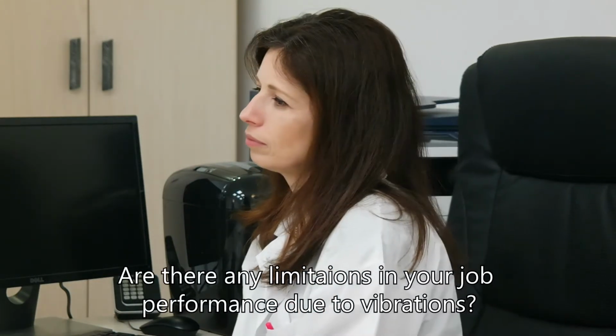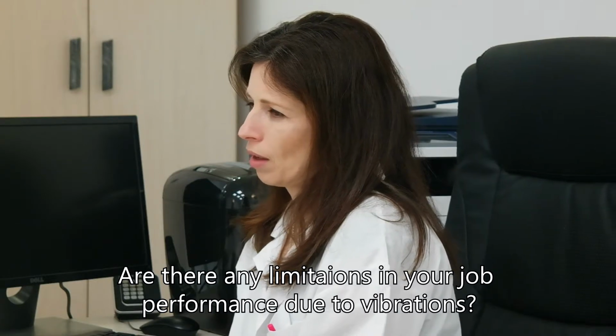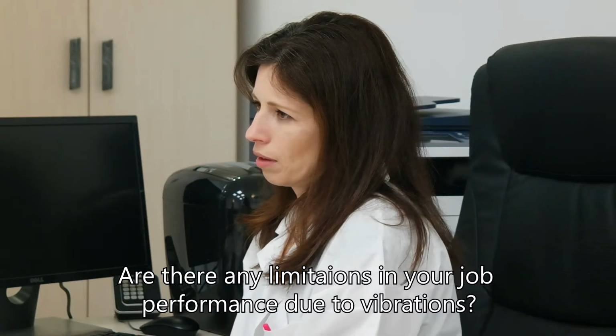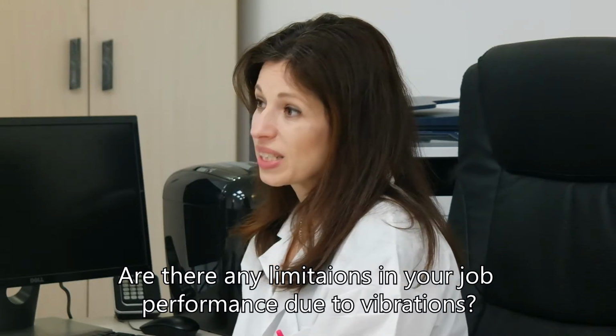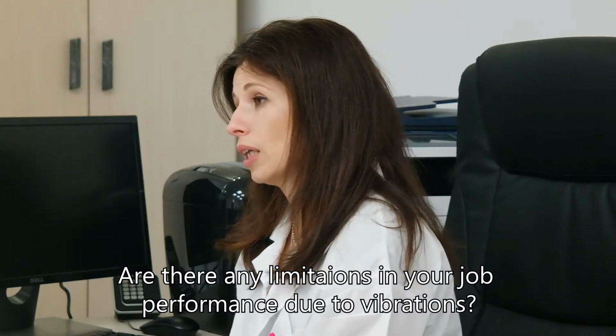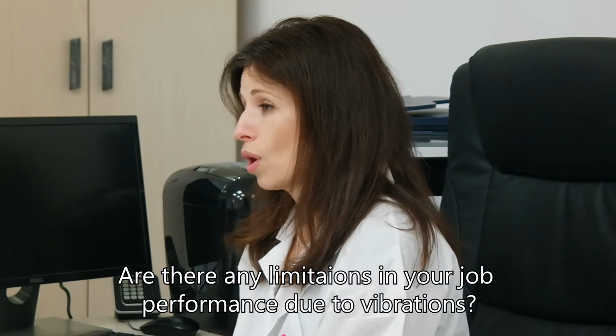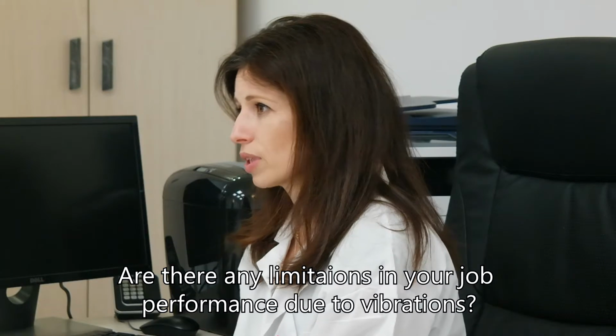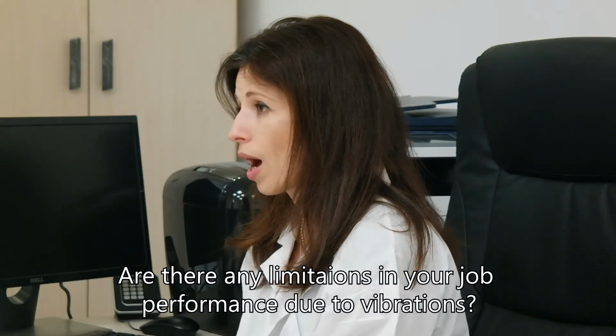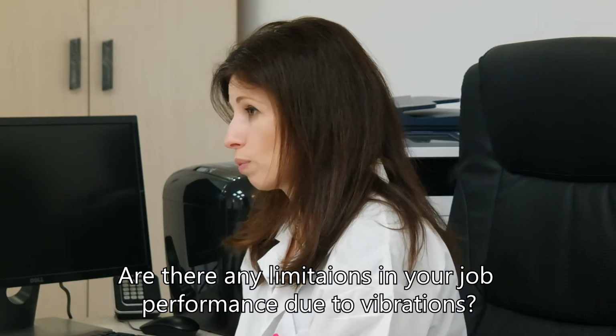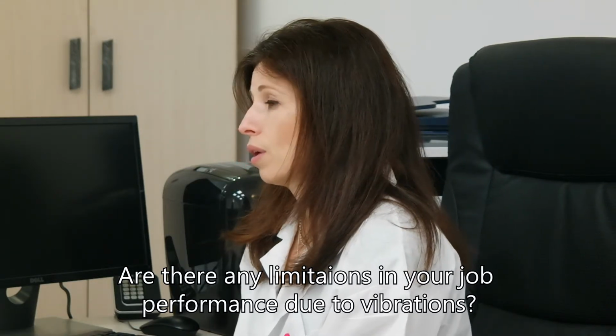Okay. Are there any limitations or constraints of your job due to vibration issues? When an IVF lab is designed, it is very important to take the vibration issue into account and not to build it close to a railway station, a bus station or a highway, not only because of the pollution but also because of the vibrations. In addition, for example, we never put a centrifuge on the same table as the manipulation system. They are separate tables, usually far from each other, in order to reduce vibration.